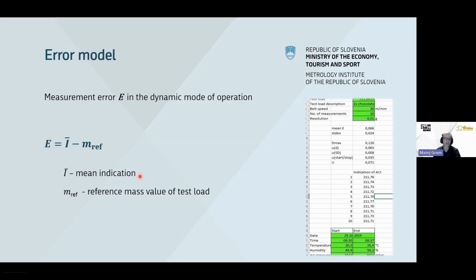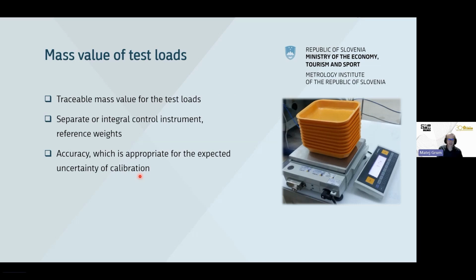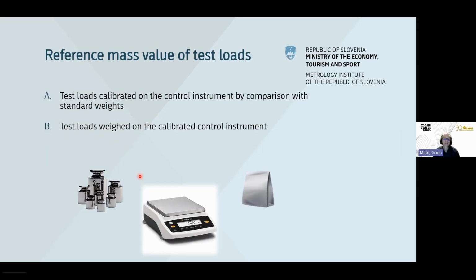First of all, I would like to say something about the reference mass value of the test load. Of course, this mass must be traceable, and it can be defined on a separate instrument, which is usually a non-automatic weighing instrument, or by an integral instrument. This is the automatic instrument which is calibrated, but it must be used in the static mode of operation. The guide doesn't define the accuracy of such measurements and the accuracy of a control instrument, but the calibration laboratory must be aware of the expectation of the client and the possibilities of the calibrated instrument. So basically the accuracy depends on the expected uncertainty of calibration.